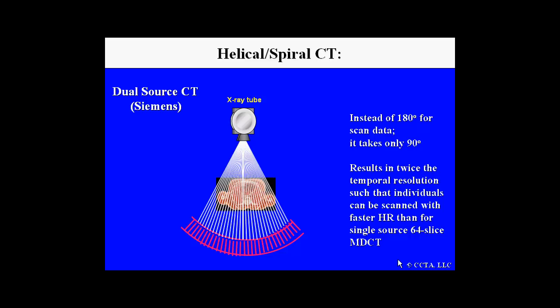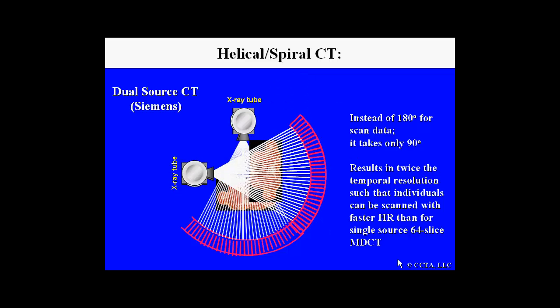Improvements in temporal resolution can be accomplished using the Siemens dual-source scanner, which results in twice the temporal resolution, such that it only takes a 90-degree rotation of each of the two heads, thus producing the individual 180 degrees required for scan reconstruction.